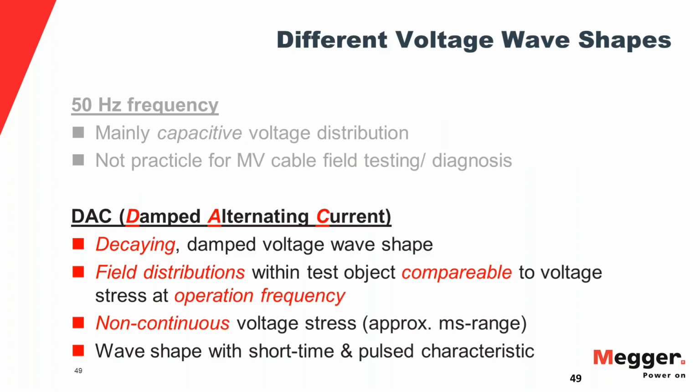And then what voltage waveforms are available from your test set? And this is actually very important. This is kind of like the most important thing. You have 3 voltages these days that you can do PD testing with. The 50-60 hertz is pretty much non-applicable, because a long cable is a huge capacitor.